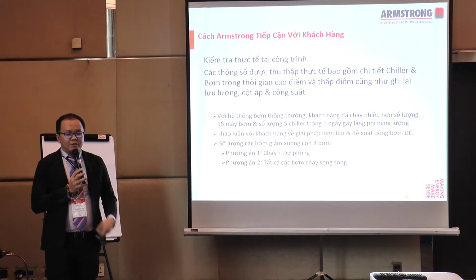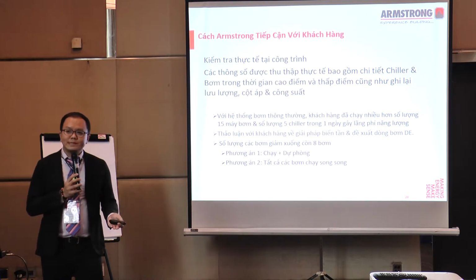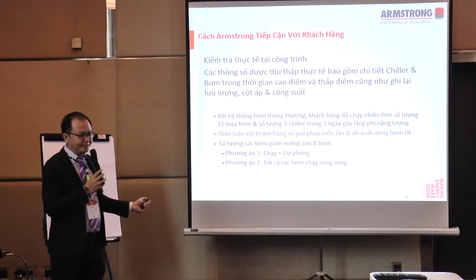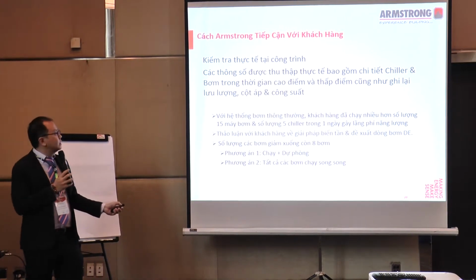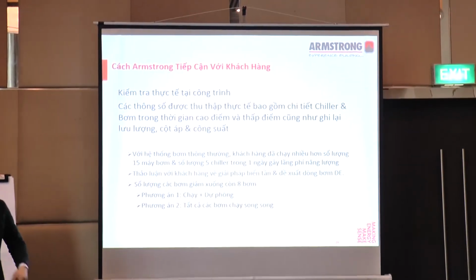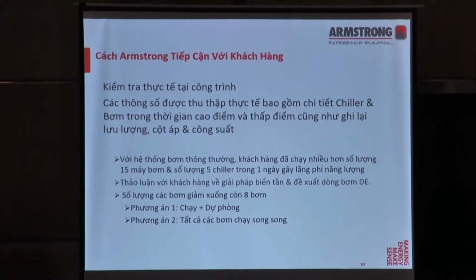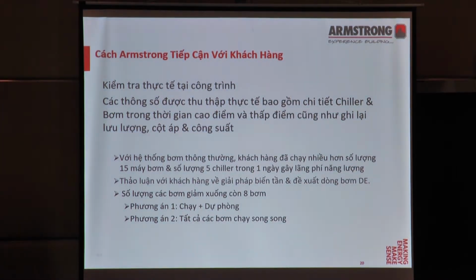So what we did from the Armstrong approach is, of course, we go to the site, we see and audit the place. Then we look at all the existing chillers, all the existing operations, the peak time and non-peak, and then we actually measure it. From there we realize how they're running the chillers using the 15 pumps and 5 chillers, and how it ends up wasting energy. Because understand, you're not running at 100% capability all the time. So a lot of times you end up wasting a lot of energy when you power on the chiller or the pumps.